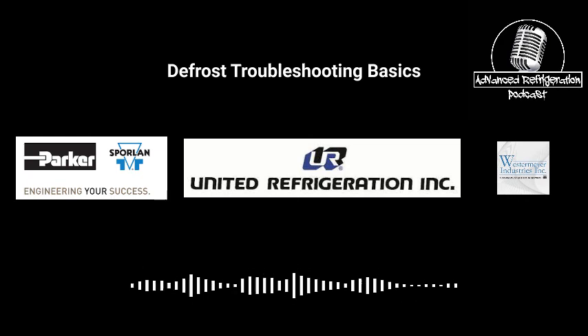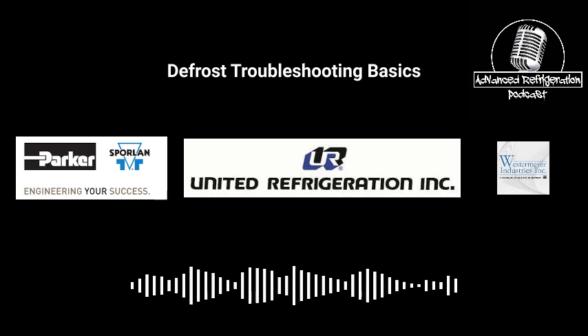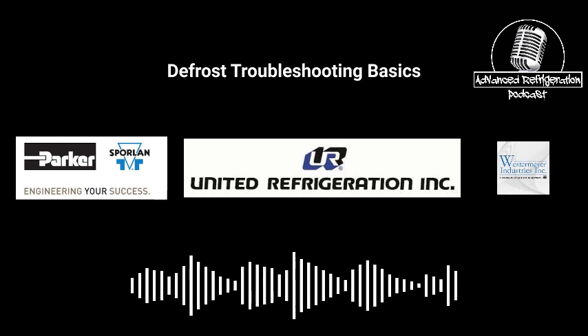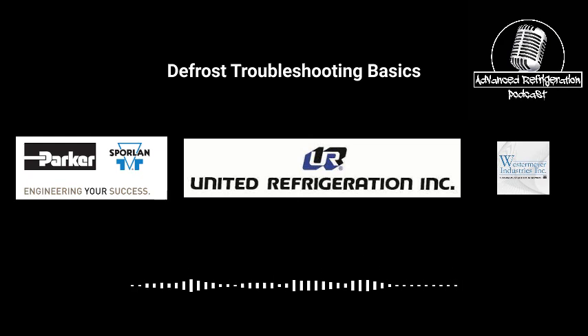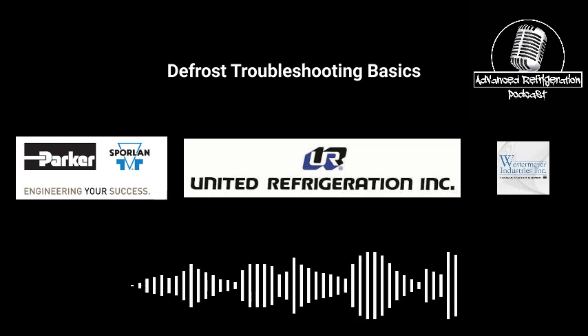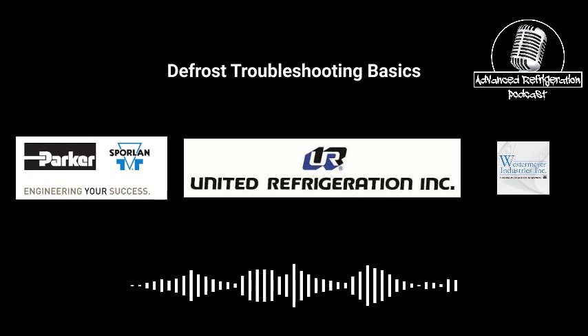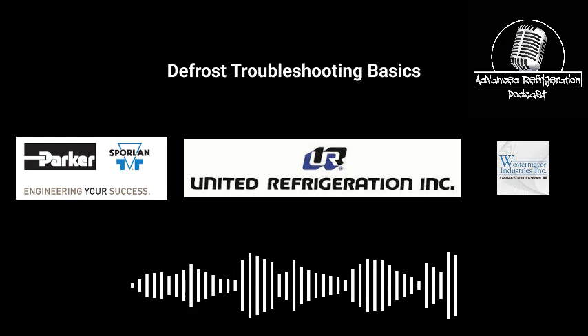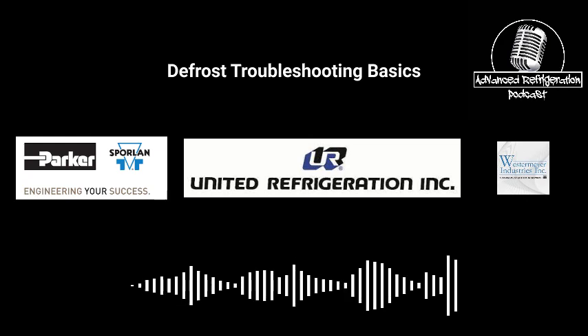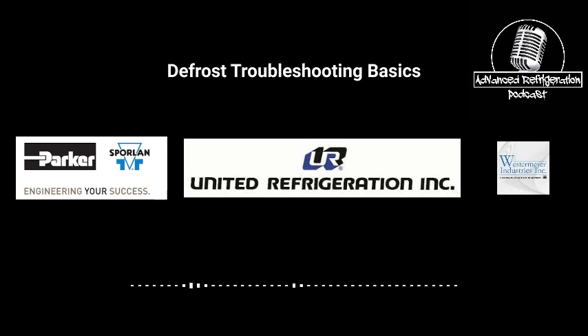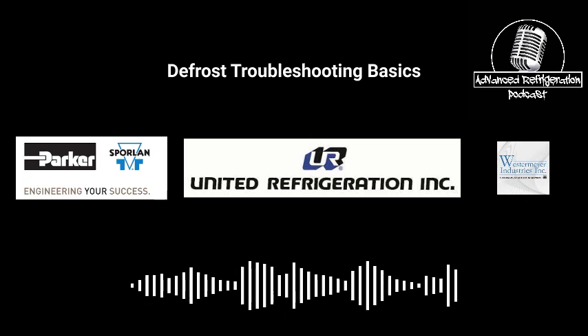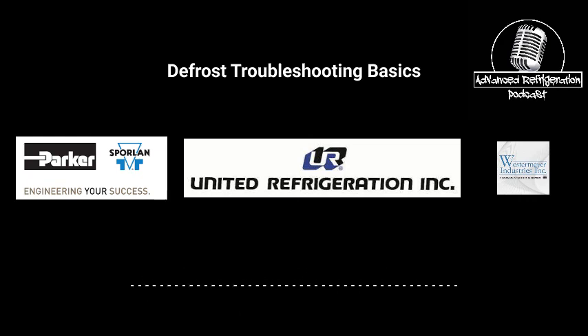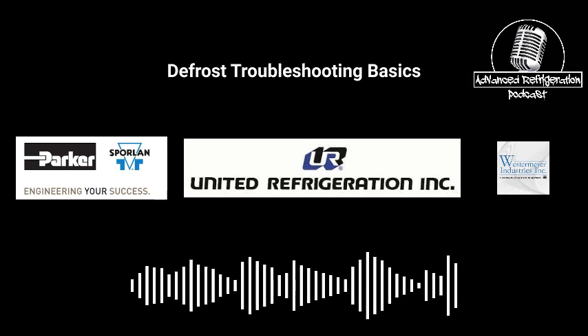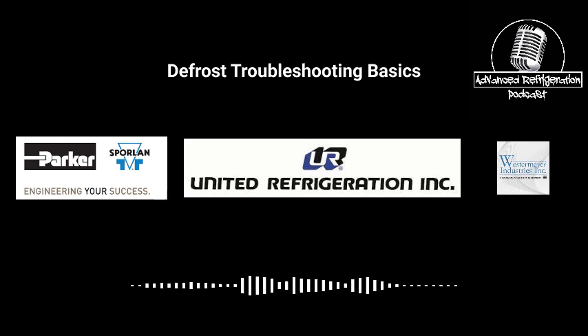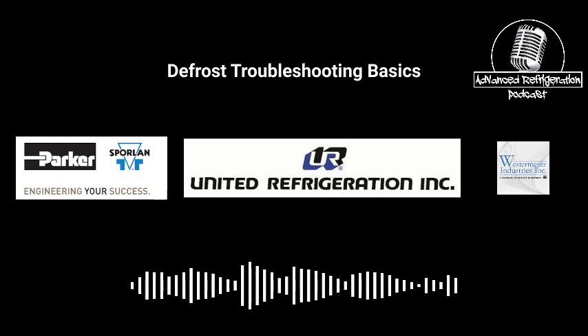True. Very true. So since we're talking about all basic parts of defrost, you want to start first with just regular off time. We'll go from there. So off time, guys, there are a lot of ways to accomplish it, but it's all the same in the end. Off time defrost, what are we doing? We're just turning off exactly what it says. We're just turning off the refrigeration, whether it's a compressor, a solenoid, an EPR, a stepper valve, whatever it is, we are just turning off that application in order to defrost it.